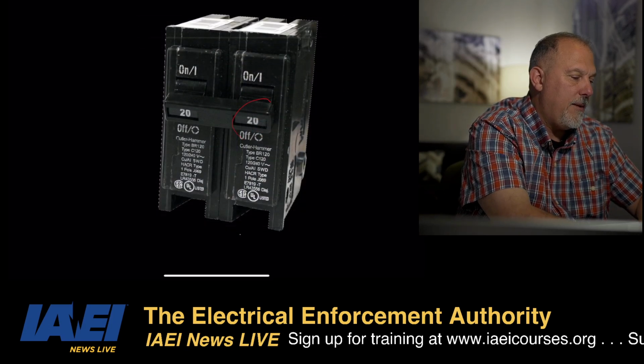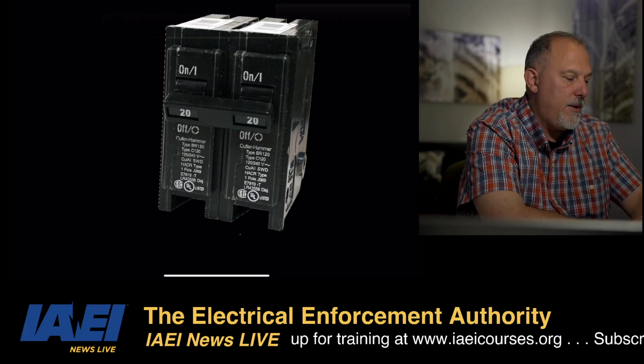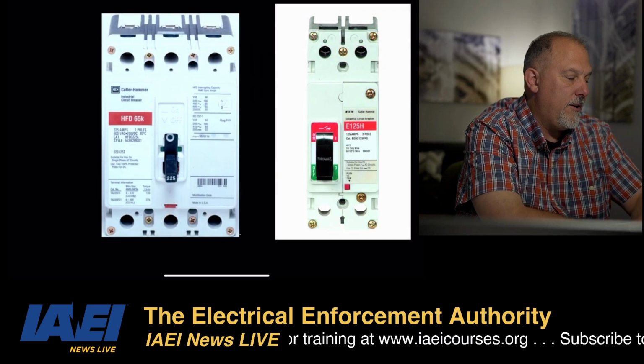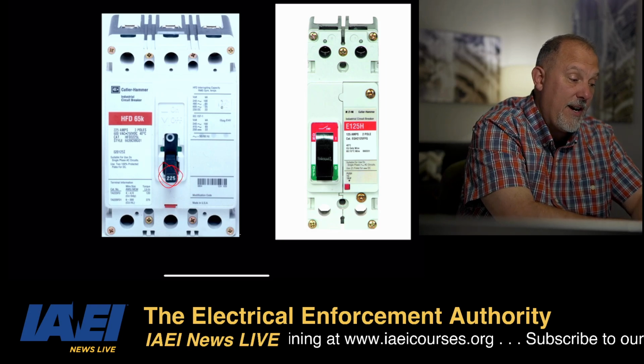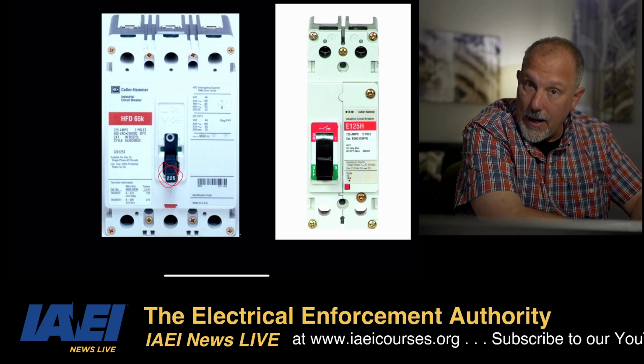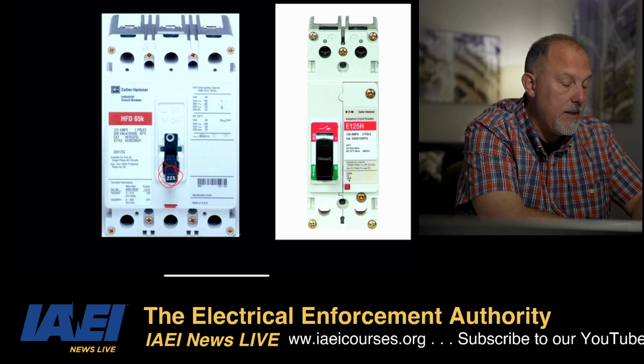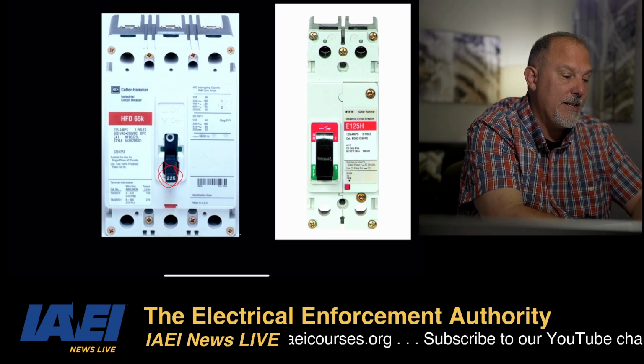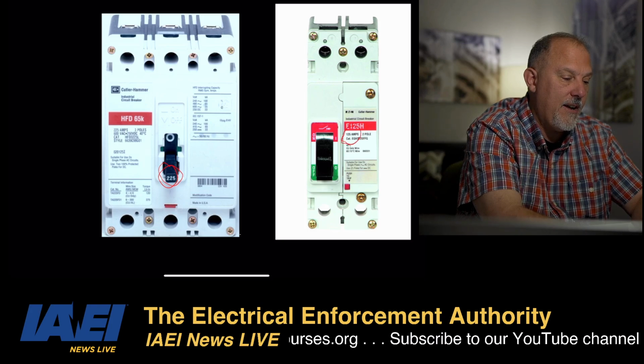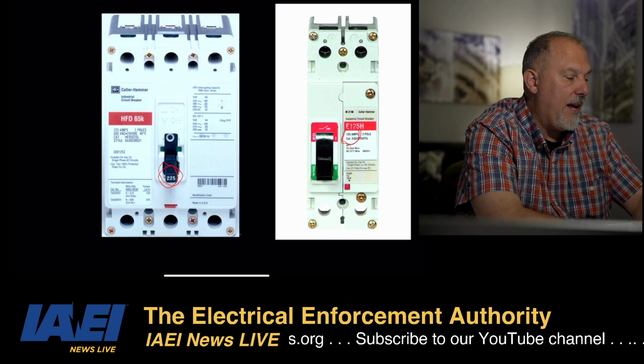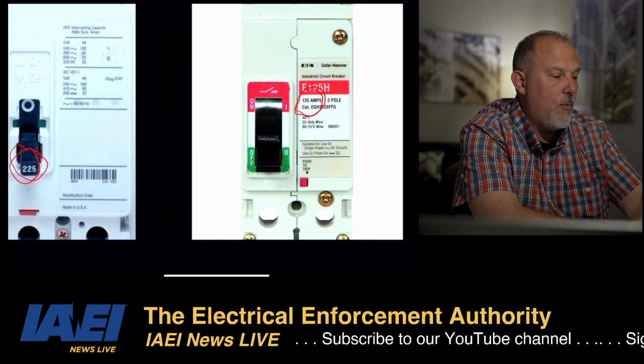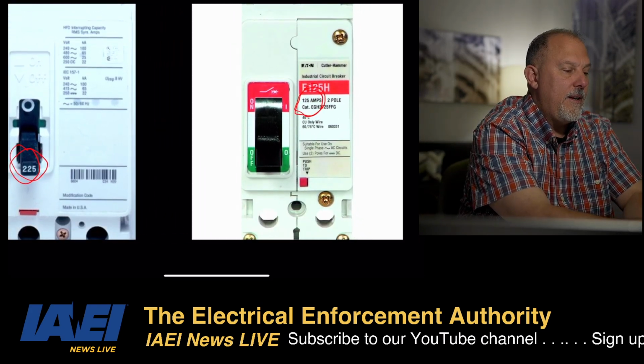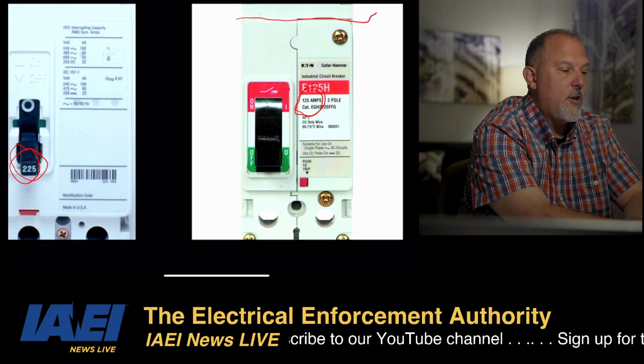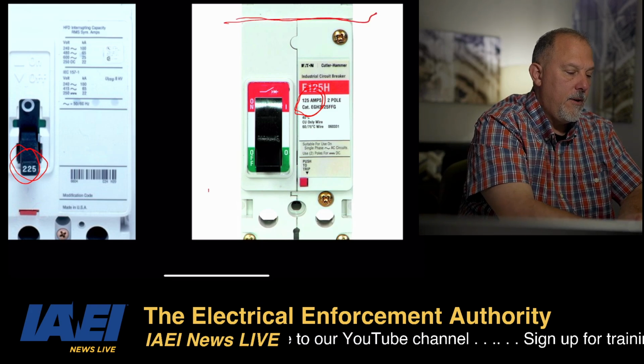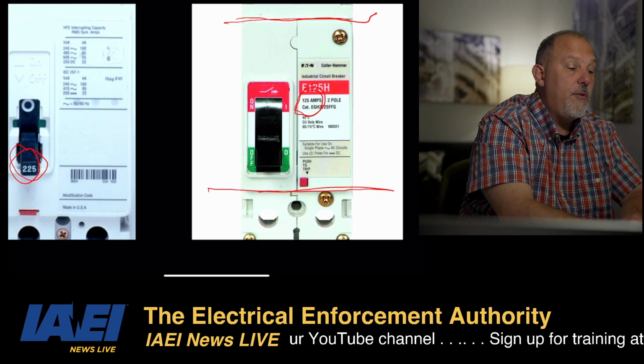There's your 20 amps, visible with the dead front on. Now there's a 225. That is not required to be there, because remember the standard says 100 amps or less. Here's 125. Now we could have a debate and argument. I don't know where. It looks like the escutcheon would go right in here. It looks like this would protrude through the dead front.